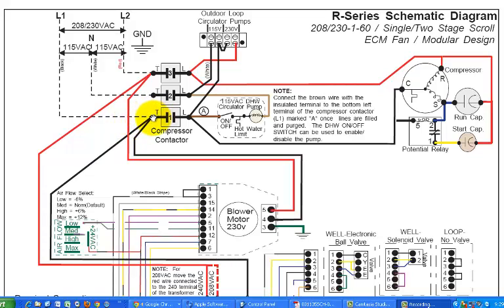Now, what we see here then is the compressor contactor, and actually that's where these wires are going to be fed into. The electrician is going to bring the line wires in, tie them into the compressor contactor, and compress the screw down to hold them solidly in place. And I stress that because that's fairly important that that be done effectively. We don't want to have those loose at all. The compressor contactor itself, we're going to get into details about that in another video, but for now, what we really want to think of it as is a big switch.